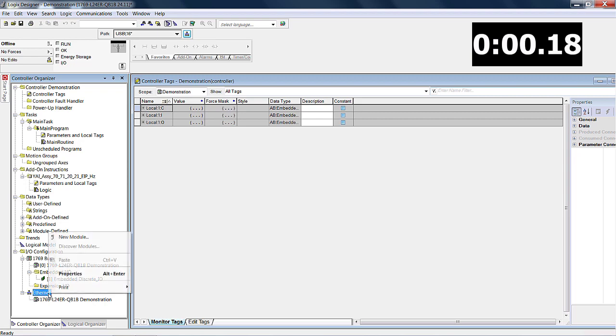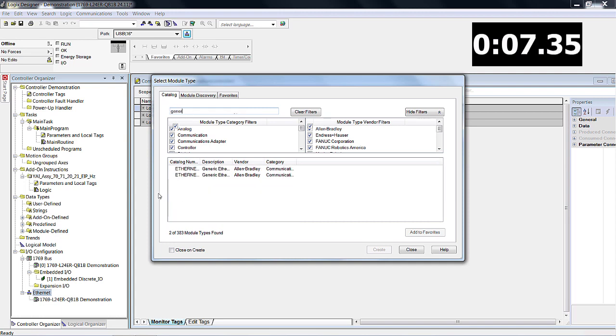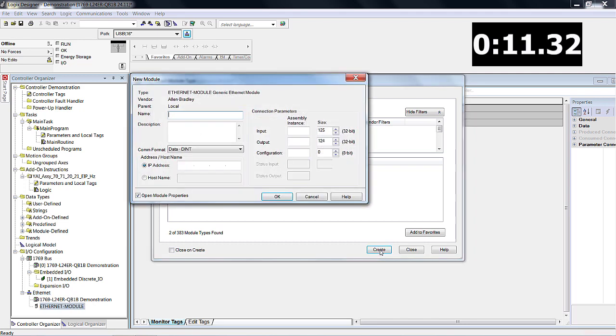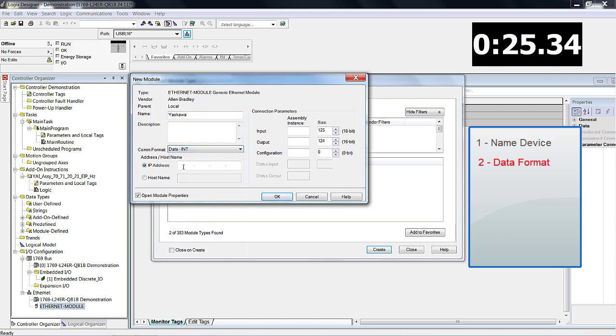First, we'll right-click on the Ethernet icon and select New Module. In the pop-up window, click the search box and search for Generic Ethernet Module. Select it in the results pane. The New Module window pops up and we can begin our 7 steps. Step 1: give the node a name — we will call ours simply Yaskawa. Step 2: choose the Comm Format by selecting data-int. Step 3: set the IP address of the node to 192.168.1.20.